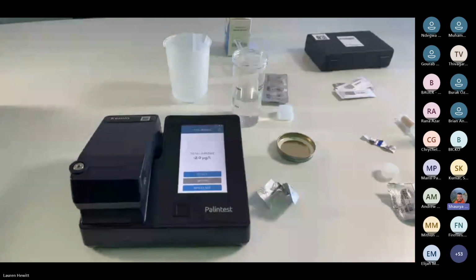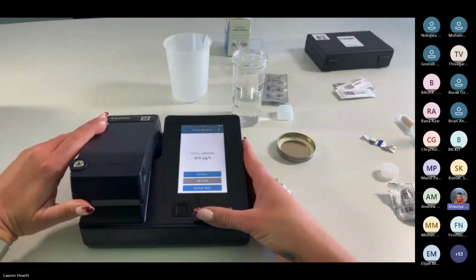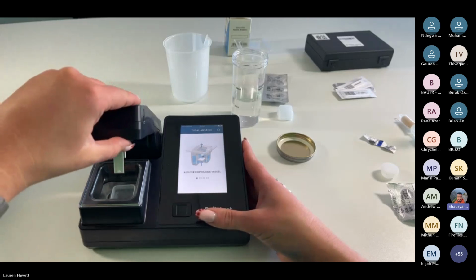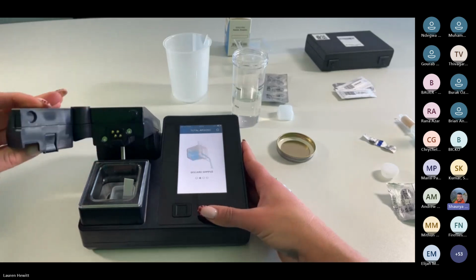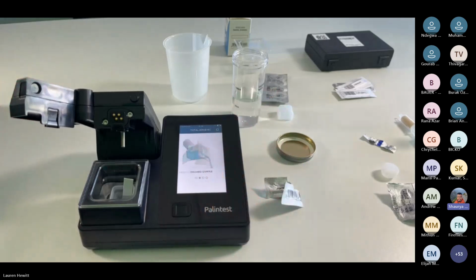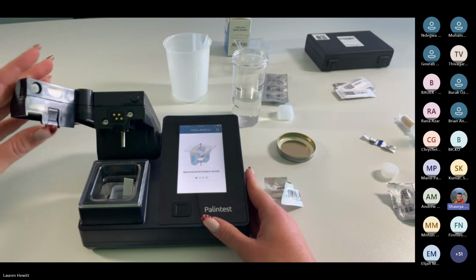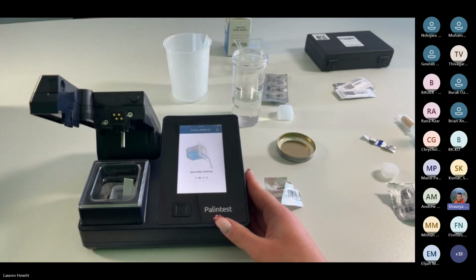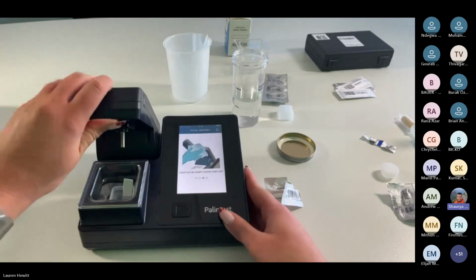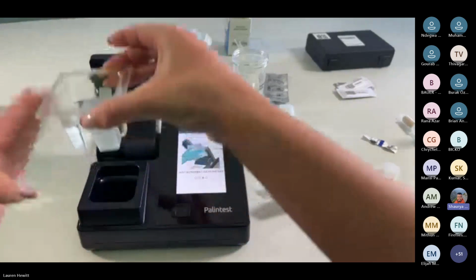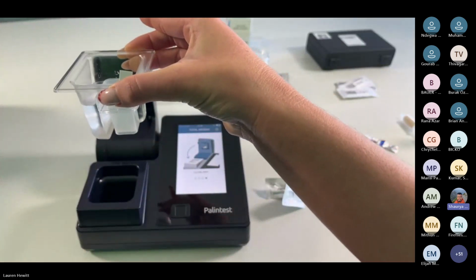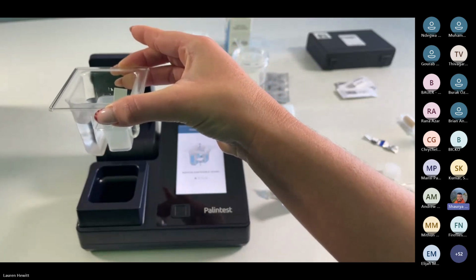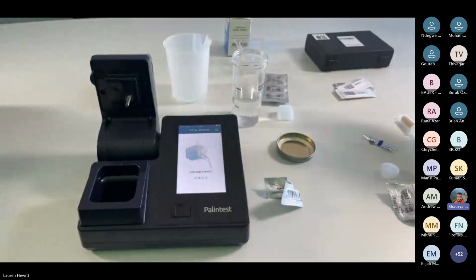So now the test is completed, we will just move on to how to remove the sample and the sensor. As you lift up, if you release the arm, the sensor simply falls into the pot. And again, this is a really good time to check the cleanliness of those contact pads, because if there are any water splashes on there or any marks at all, keeping those clean and dry makes sure accurate results are achieved. This can simply be cleaned with an alcohol wipe or a lint-free cloth, just anything that doesn't have any fibres on it. And for removing the sample itself, you simply lift out the whole container and it is ready to be disposed of. The arsenic sensors are non-hazardous, so they can be disposed of in accordance with your local regulations.